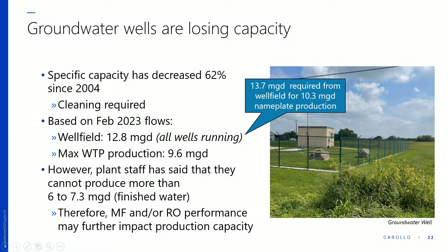But before we leave the well field, we want to talk about some of the hydraulic evaluations that we've done and the status of that. Last time we talked about this hydraulic model that we'd built and how the well field hydraulic model wasn't matching the existing conditions. The model was saying that the well field should actually produce more water. So that led us to ask questions about valves within the pipeline. And what plant staff has been able to find out was that there are some line valves in the system that are broken. They rotate, and we don't know whether they're fully opened or fully closed, or partially closed. So if they were partially closed, that could be a reason that some of the wells are underperforming.